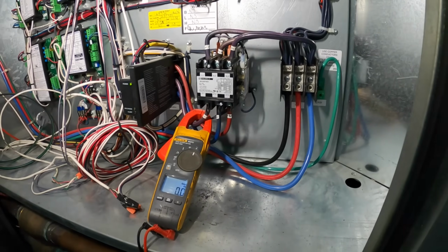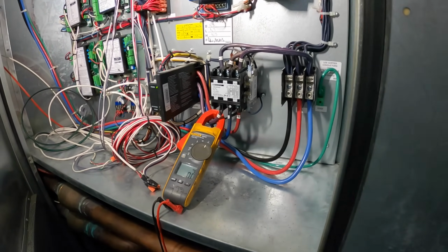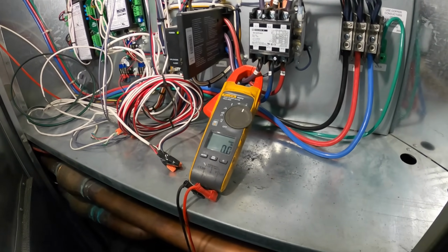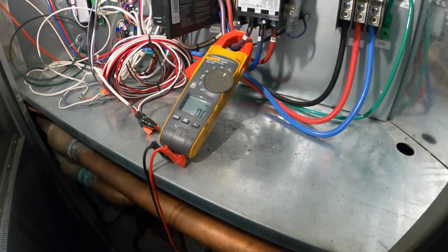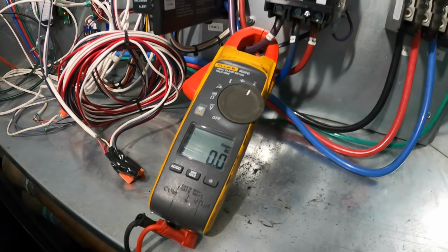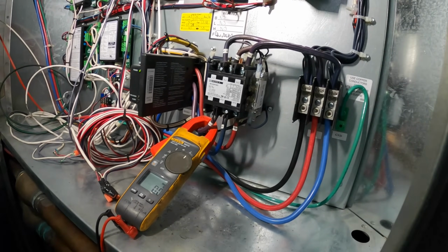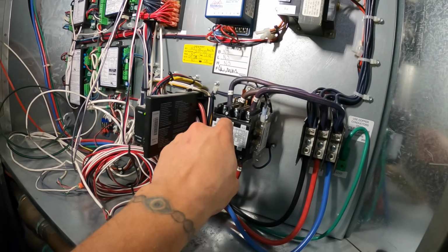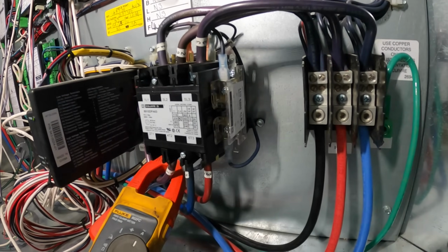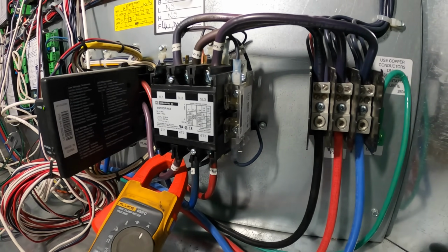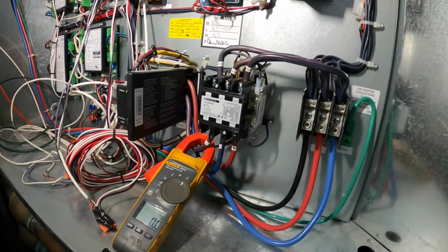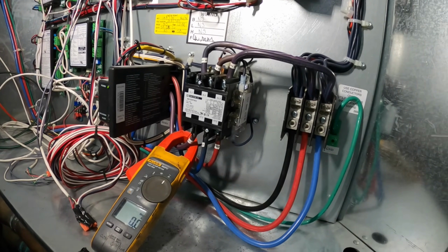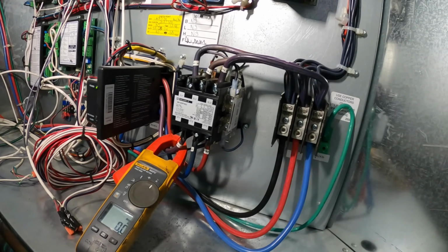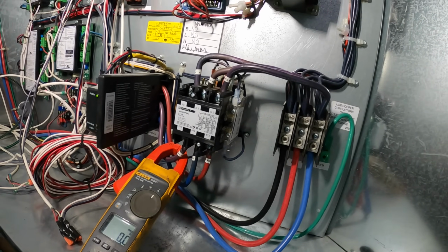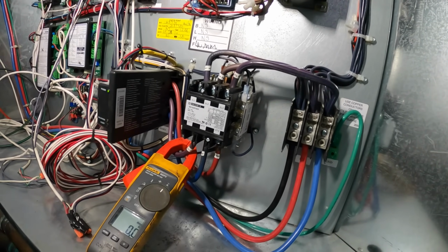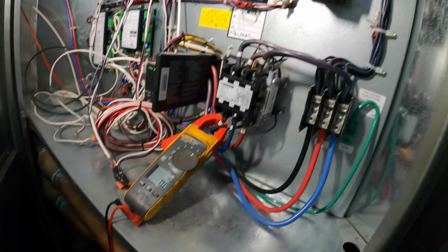It's probably going through a timer. Let's see what happens. I hear the fan ramping up a lot. Come on. Come on, come on. Let me see that plunge in. So when the contactor plunges in, the contacts over here actually, they plunge down as well. They basically normally close opens, and normally open gets closed. So we have a normally closed circuit, so when the contactor is plunged in, that should actually open.